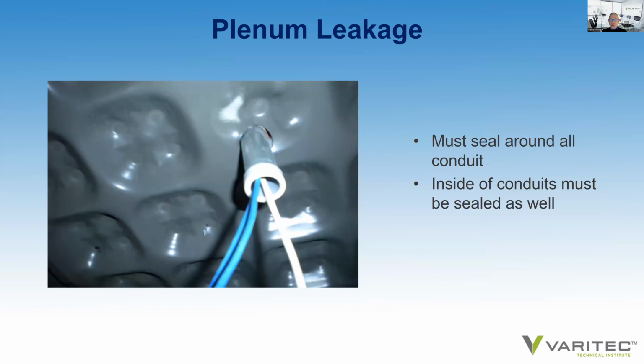You can see conduits need to be sealed. If there is a conduit up a wall that penetrates a floor tile, that has to be sealed. Otherwise, cool plenum air will get into the plenum or the wall cavity, and it will bias the thermostat. The thermostat will condition to the wall temperature and not the space temperature, which is not conducive to a successful project.